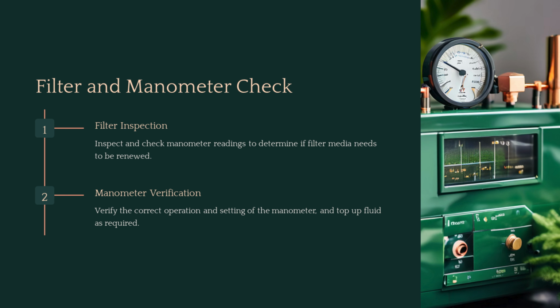The first step is to check the filter. Inspect and check manometer readings to determine if filter media needs to be renewed. Verify the correct operation and setting of the manometer and top up fluid as required.